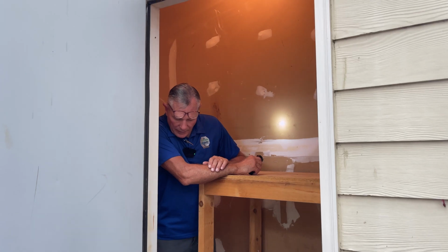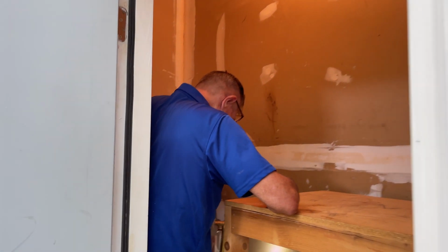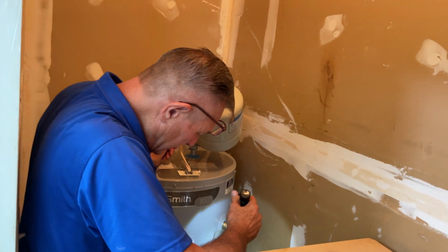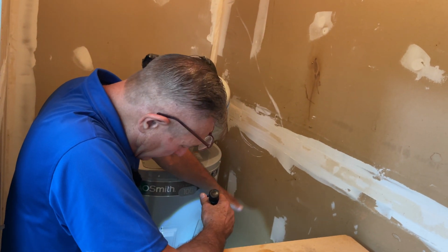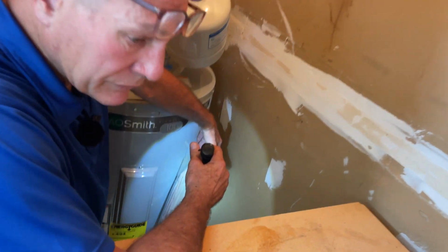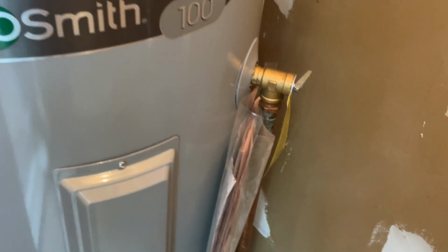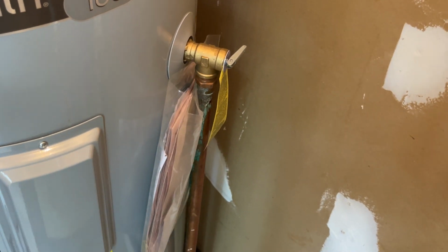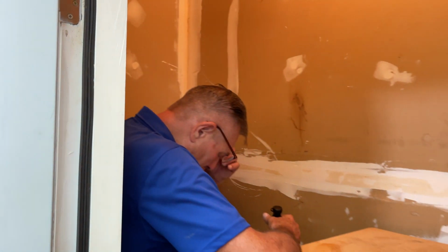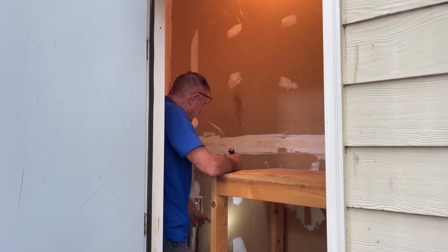All great. Now we're in the utility closet, same as the electrical panel where the water heater is located. Here we're inside, and again, we visually inspect. This is a temperature pressure TPR valve, temperature pressure relief valve. If pressure gets too high, this helps release the pressure. It goes down to the ground, 4 inches off the ground. And in here it's fine, it's a cement floor and all, but I recommend having a catch basin to catch the water, just a recommendation.